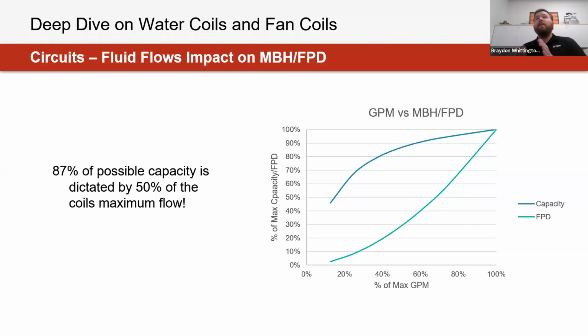So for any of you that are dealing with a situation where you're not quite getting to the targeted capacity, or you're trying to add much more fluid flow through this coil and not seeing as much gain, the reason is that a lot of the additional gain in capacity comes from that first 50%, let's say, of fluid flow passing through the coil.